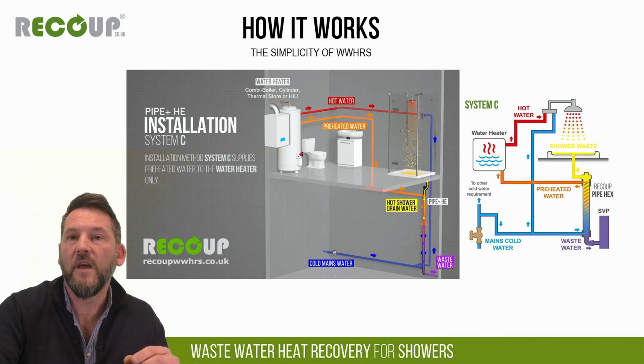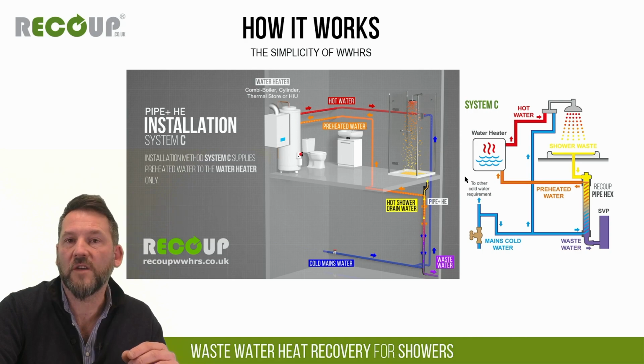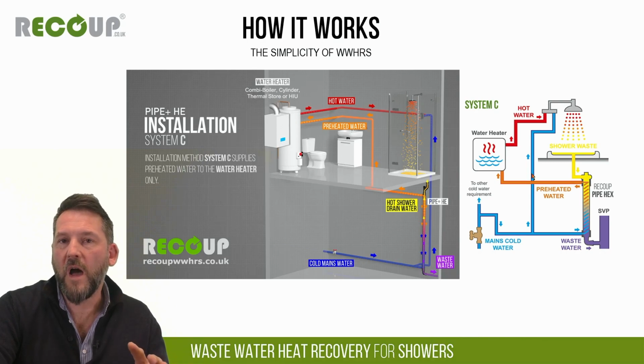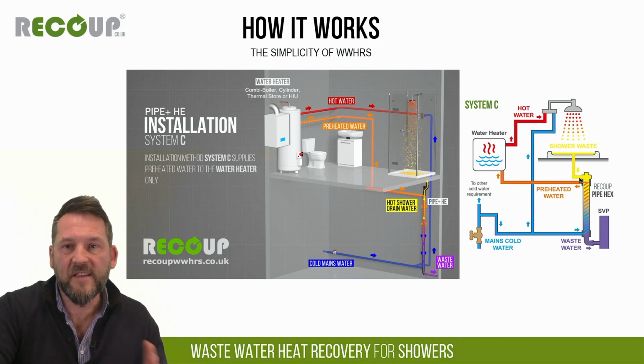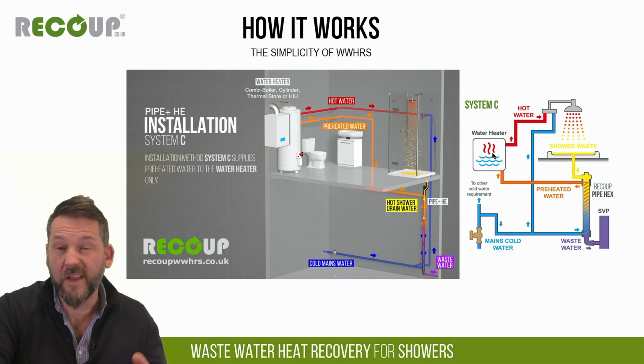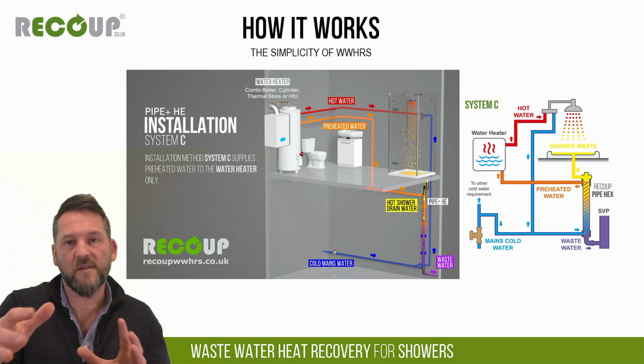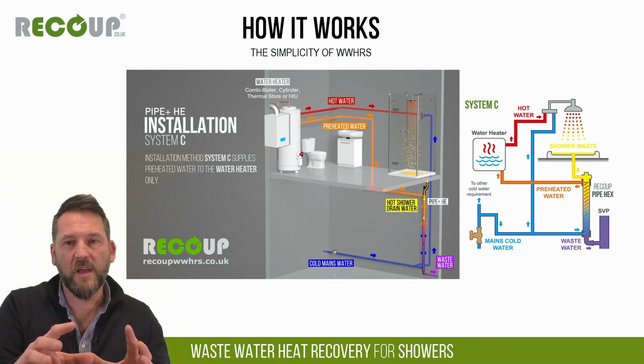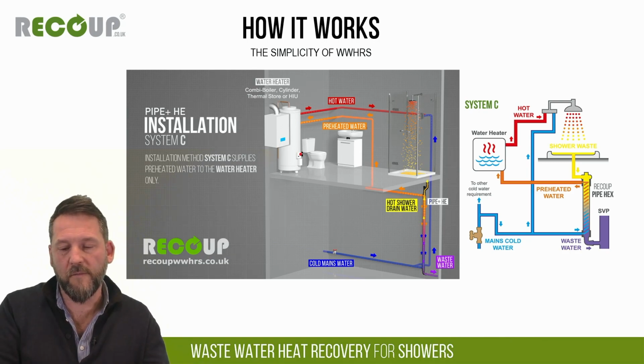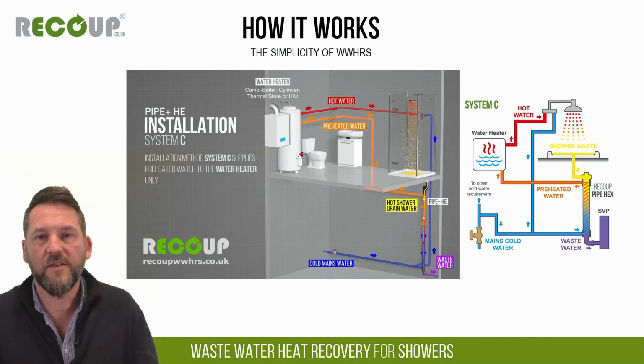And then for completeness, System C, as you may have guessed, is where we send the preheat just to the hot water source only. So this is not used so often in residential, but where you may see it, for instance, if you have a townhouse setup where you might have a second floor shower stacked above a first floor shower, the wastewater heat recovery will locate on the ground floor, and then it's probably easier and cheaper in terms of installation to just pipe through to the boiler or cylinder, which is in most cases probably going to be on the ground floor as well. So it's a solution that sits in between System A and B, but realistically in new build will probably reduce the amount of plumbing and pipe work that's required. So it's used in that respect.